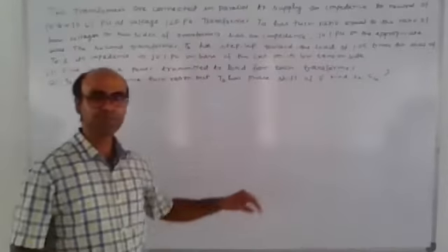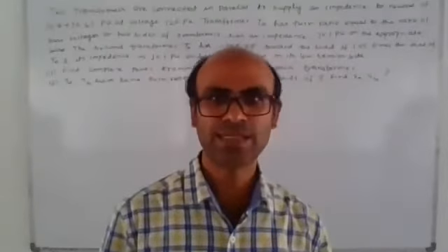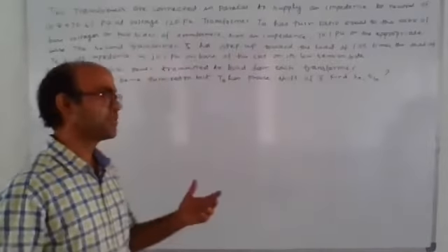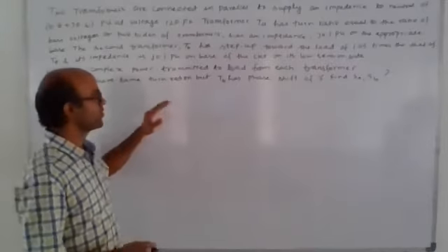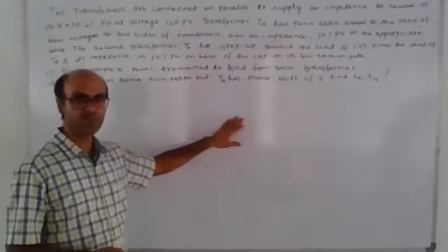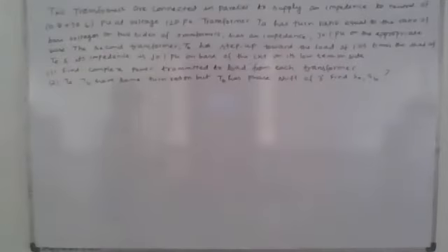Okay, so good morning. This is a question based on our previous concept. I have told you that a regulating transformer can control real power as well as reactive power. If you change the number of turns, there is a change in reactive power. If you change the phase shift in the transformer, then you can control real power. So a regulating, or we can say boosting, transformer has both features. It can control real power as well as reactive power.